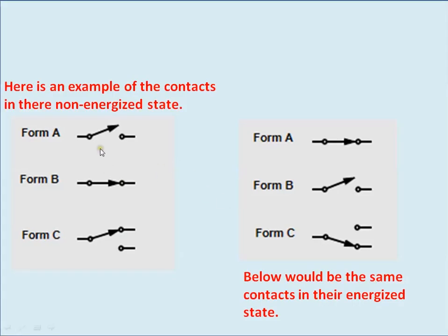This is the pictorial representation of Form A, Form B, and Form C contact devices. Form A is normally open, Form B is normally closed, and Form C has one NC and one NO. In the energized state, the Form A contact becomes NC, Form B becomes NO, and the Form C contacts change over from NO to NC and NC to NO.